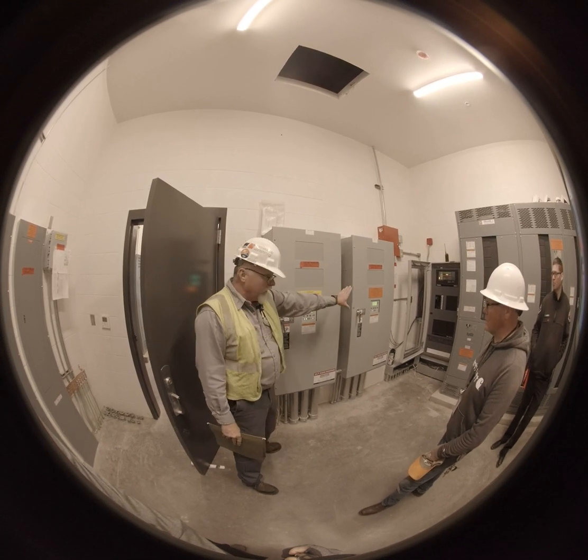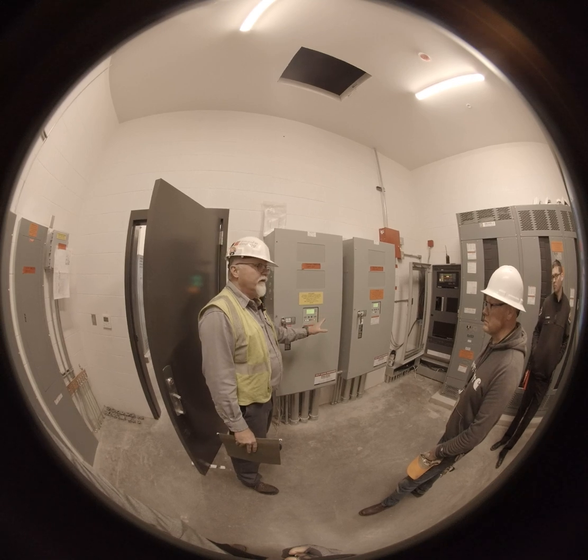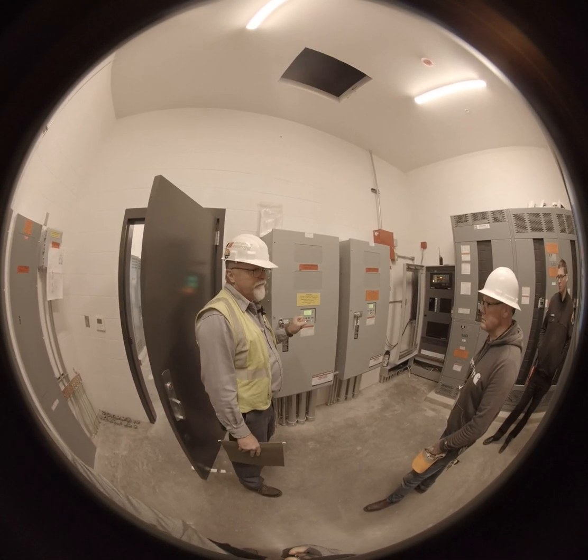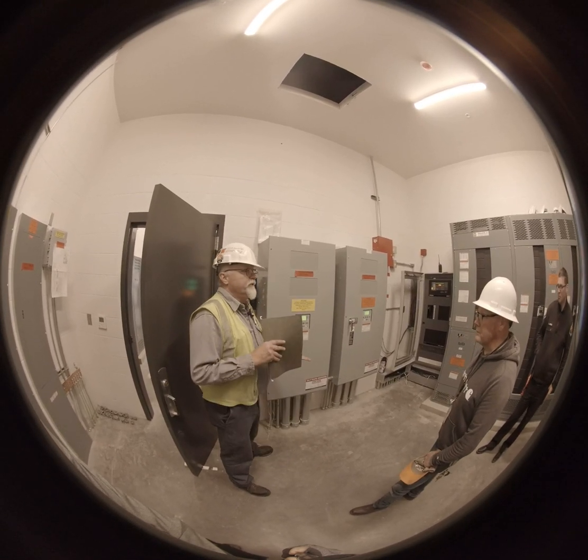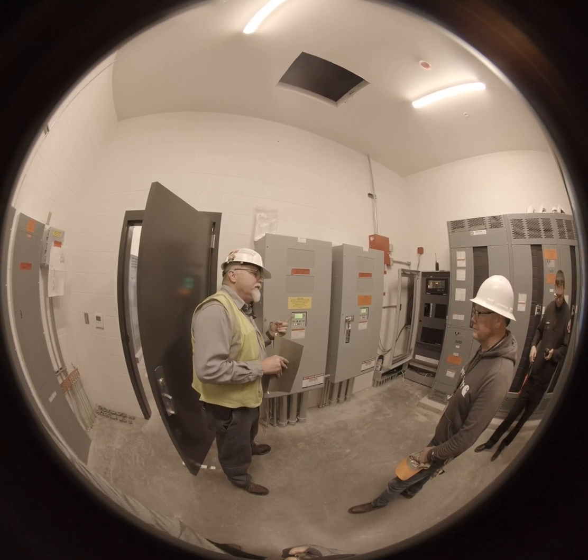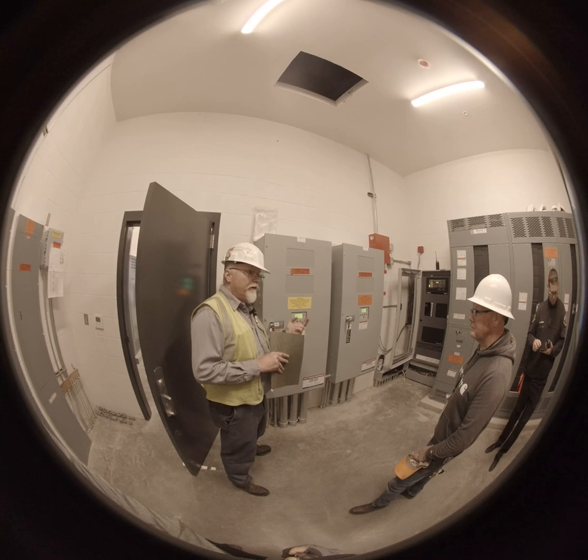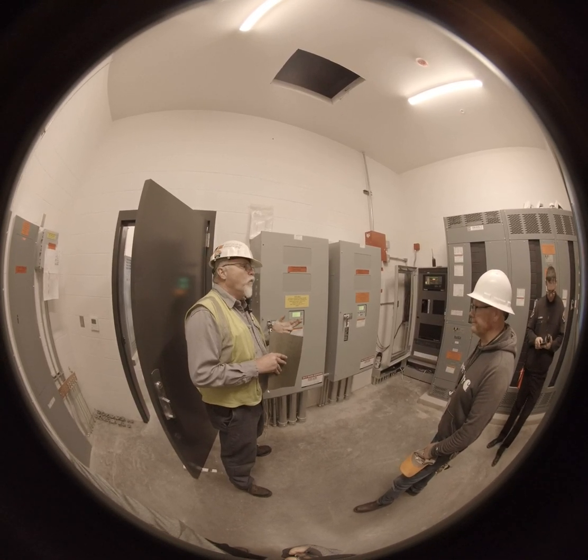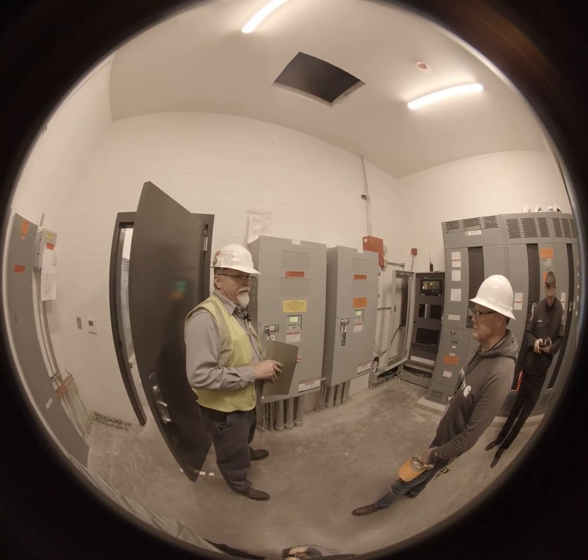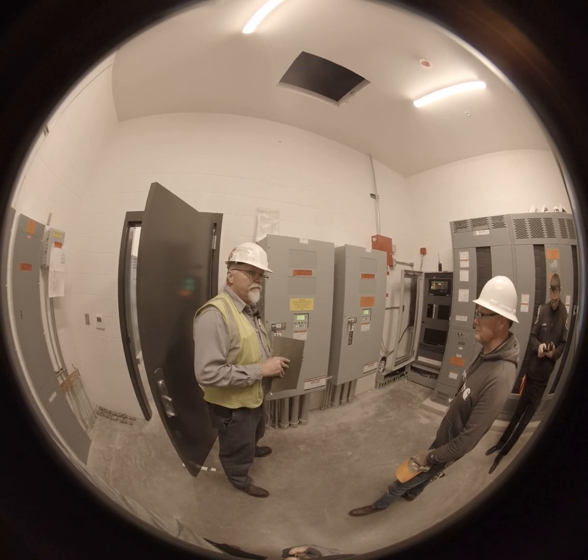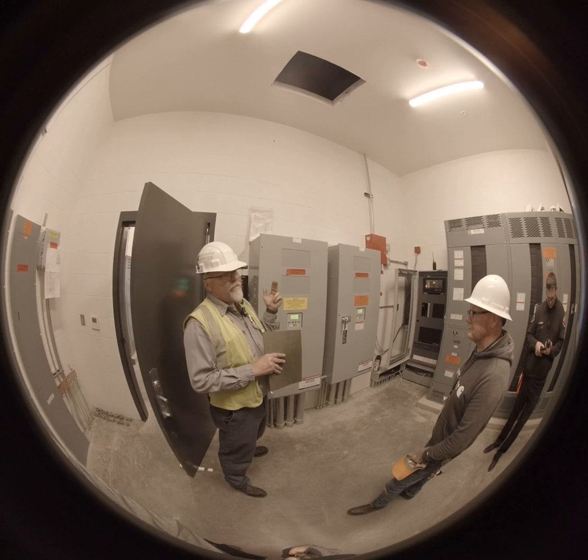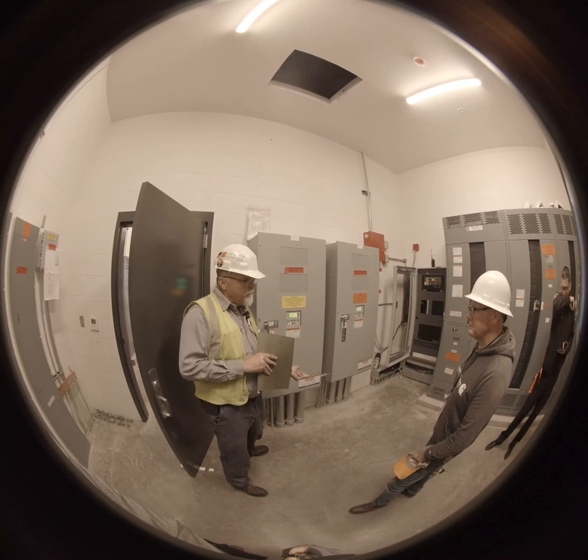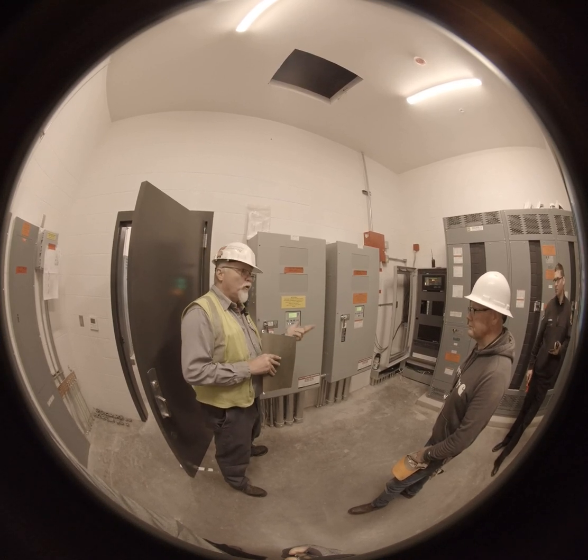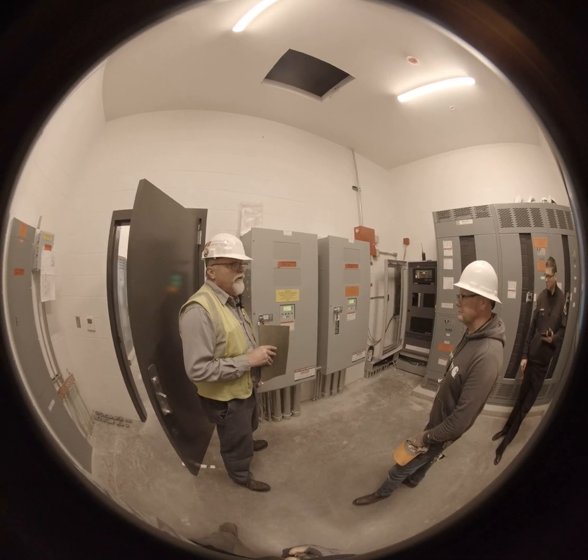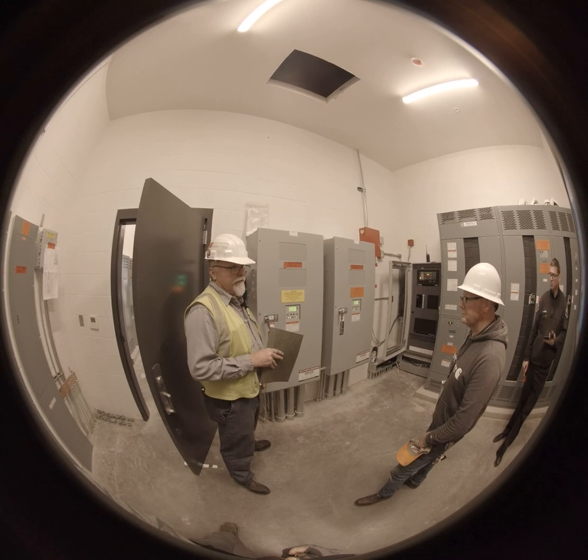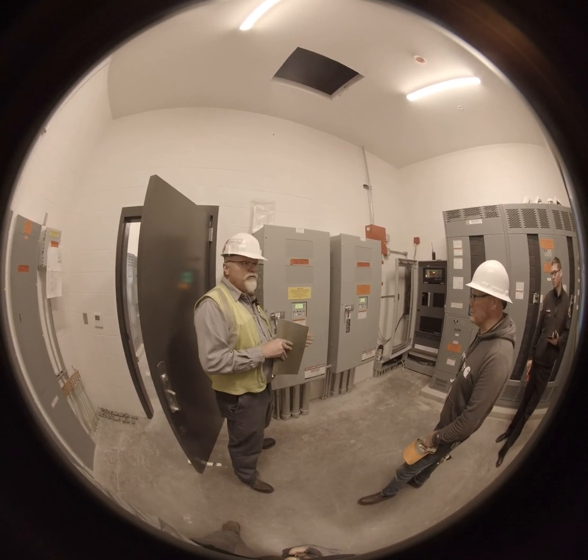That's only in this switch. The life safety switch does not have any loads of that magnitude on it. It's just a little guy. So he has just his standard time delays. Your normal transition on a transfer switch is you have your time delay for engine start. That is utilized so that if you have a blip rather than an actual outage, it's not going to start the gen. Once it has passed that time delay, which is typically 3 seconds, it's going to say, I'm going to start the gen. Now, once it starts the gen, if the utility power comes back before the gen gets up to acceptable voltage and speed, or the time delay times out, which I have set at 0, then it would stop everything and just go into cooldown. But if it makes it past that, then it's going to do the transition to secondary source.